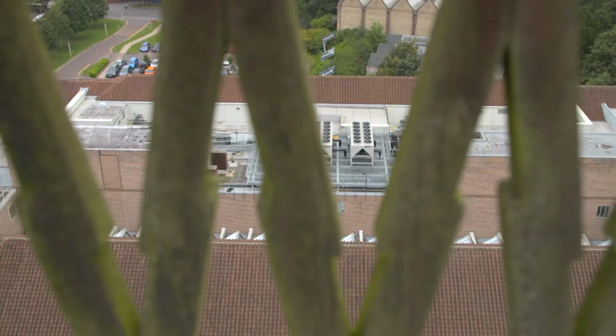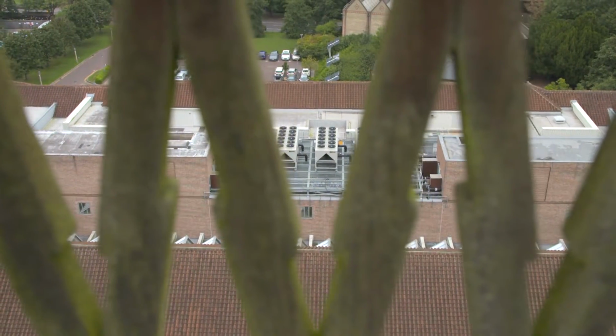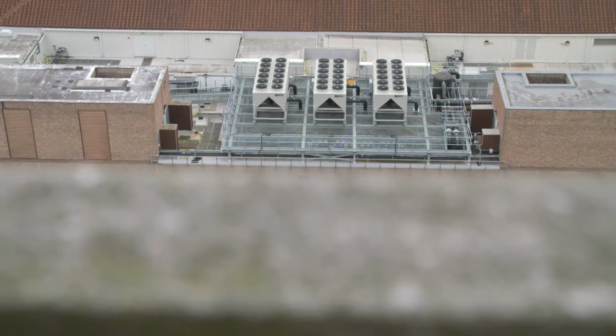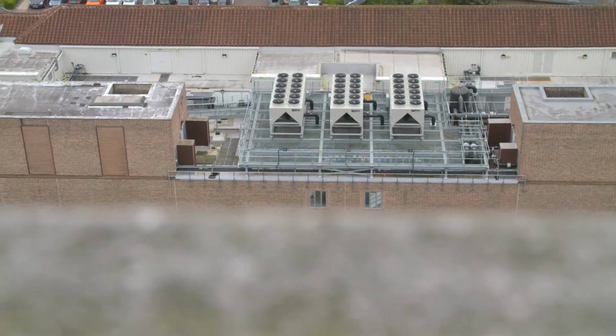The condensers were on the rooftop, and the air handlers they served were in the plant room at level 5. By centralising the systems and putting everything on the roof, where we had a number of air handling plant and other chillers, we had 7 in total, and we reduced down to 3.